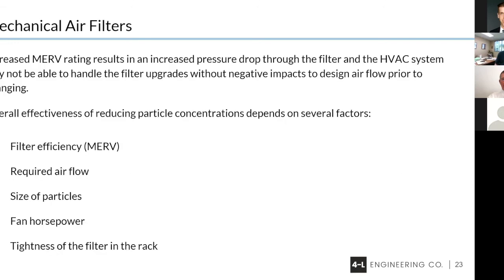Next slide. One of the things I need to talk about when people start changing their filters is that they need to be conscious that, one, your air conditioning unit can only handle a certain grade of filter. And if you increase the MERV rating too high, you're going to drastically reduce the airflow. It's going to catch the particles and the fan horsepower is going to go up. It's important that you search and see how efficient a filter you can put in your unit and have it effectively work and provide the airflow that you want, collect the particles that you want, and not exceed the horsepower rating of the fan motor.